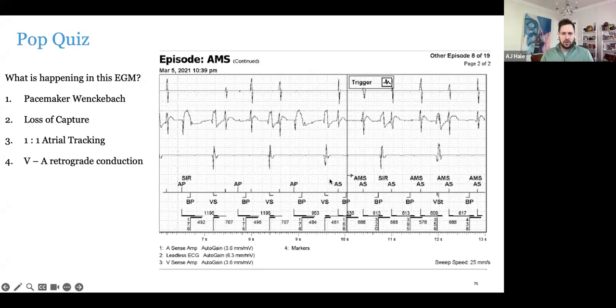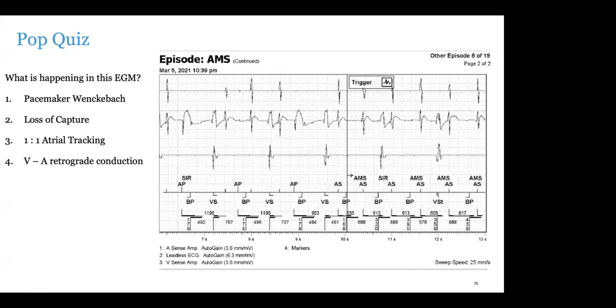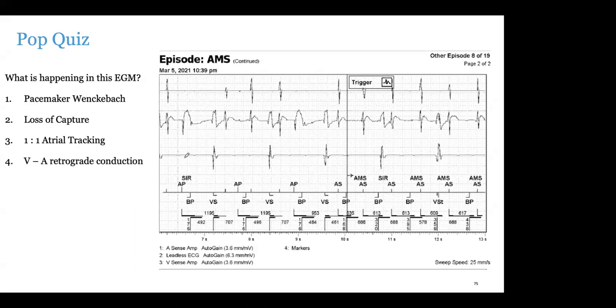Jared: There's also clearly an issue with the atrial lead — we've got loss of atrial capture as well. AJ: Dead on. And as Jared said about the leadless ECG, I agree — the first thing I do is turn it off. It can be misleading. What I like to do is have a unipolar EGM showing the evoked response across the myocardium. Remember that your sense amps are a near field, unfiltered bipolar. It's great for seeing what the device sees, but for actual diagnosis it's not ideal. You really can't tell the difference between a PVC and an intrinsic event using a sense amp channel. So we've got both loss of atrial and ventricular capture here.